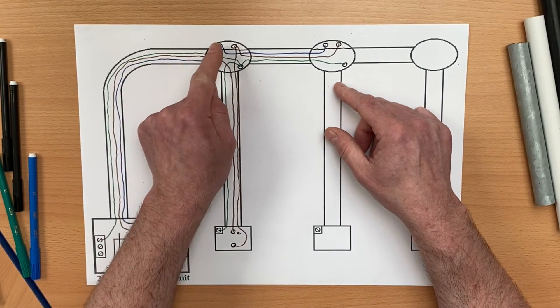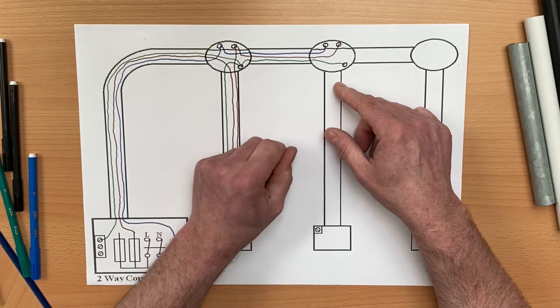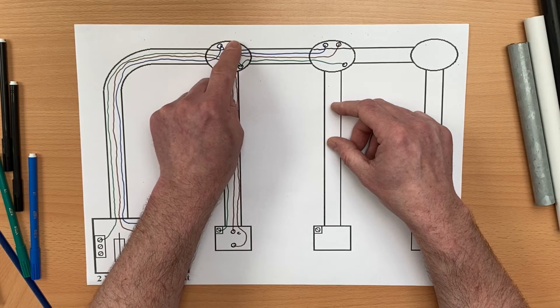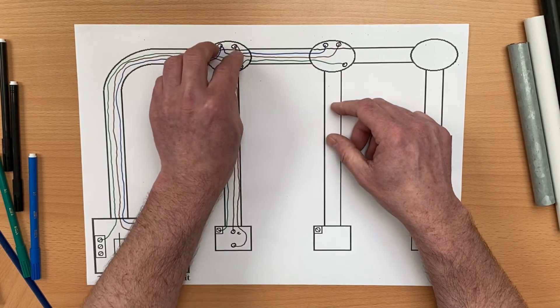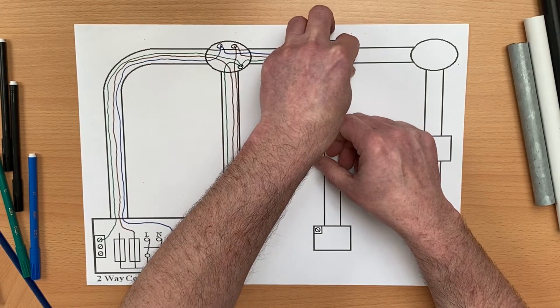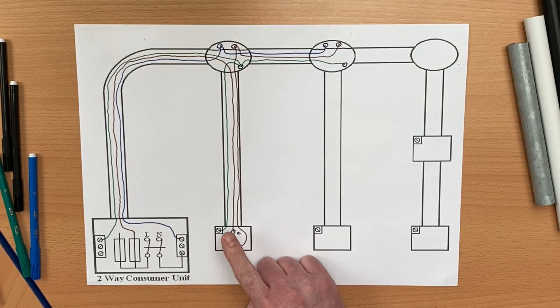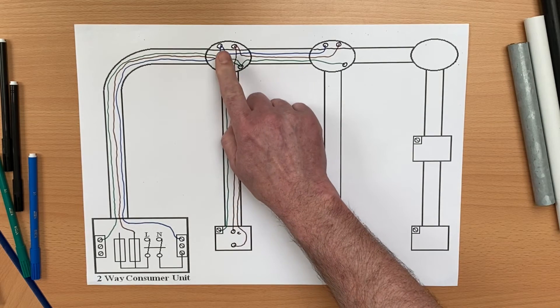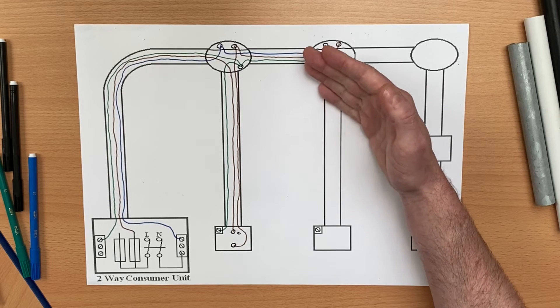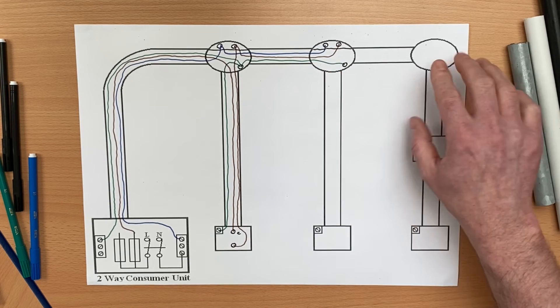When I turn on this switch, I turn on this light, and because I've shared a neutral across—it needs a neutral, a CPC across to make it safe—and I've shared the switching line conductor across to here, when this lamp illuminates, might be a fluorescent light fitting, this one here will also illuminate. Meaning that this one-way switch now turns on this light and this light.